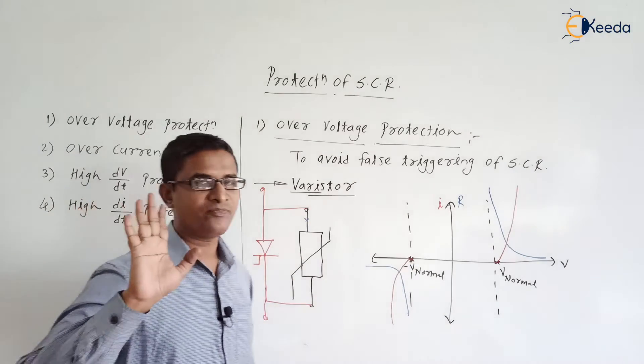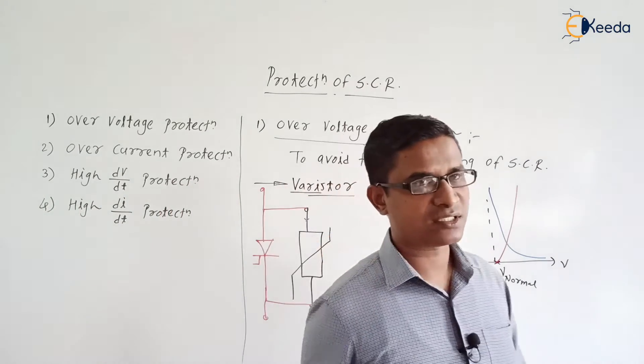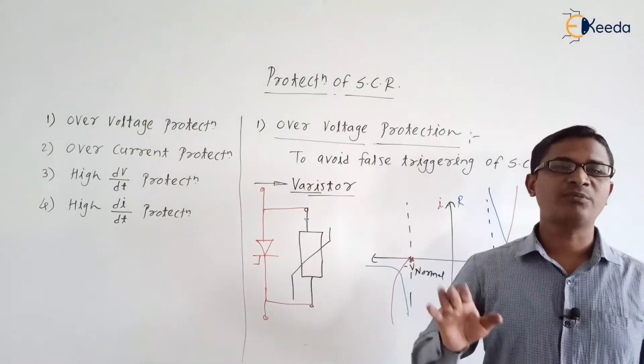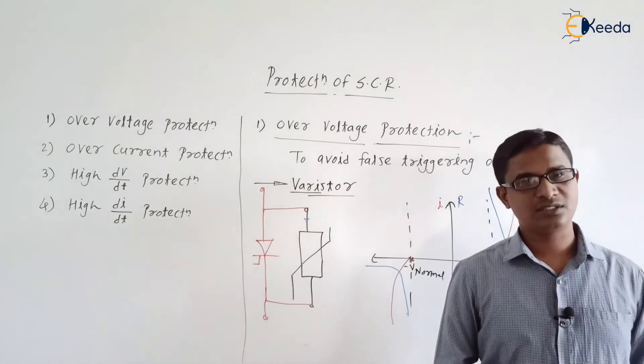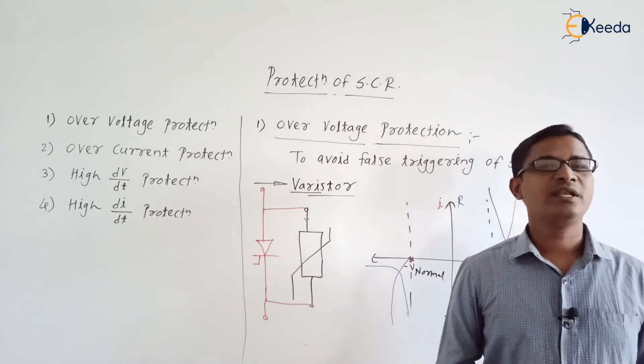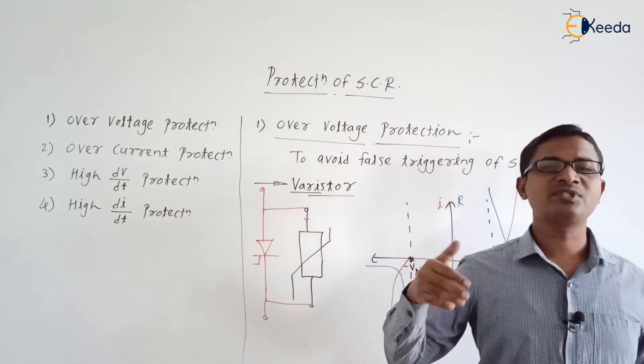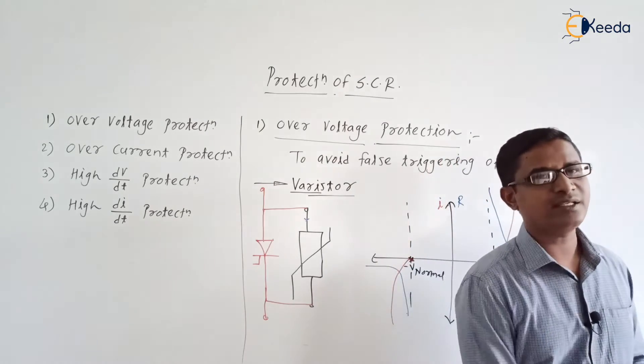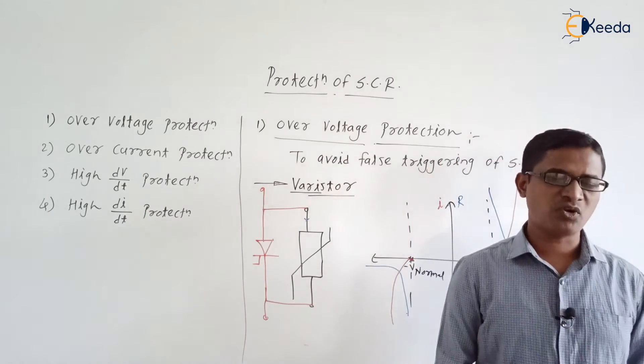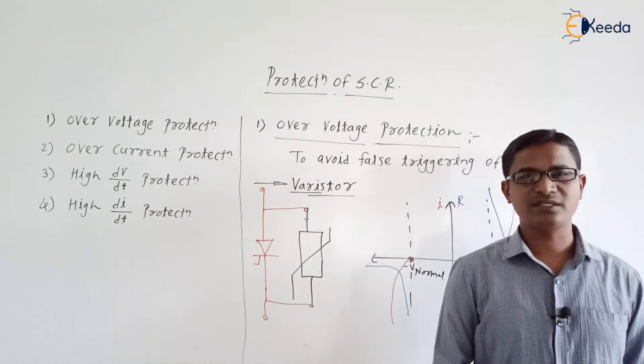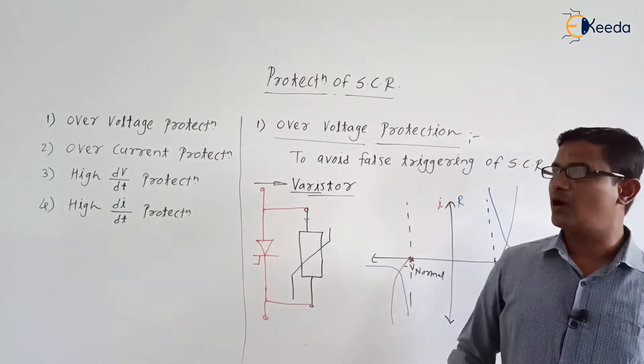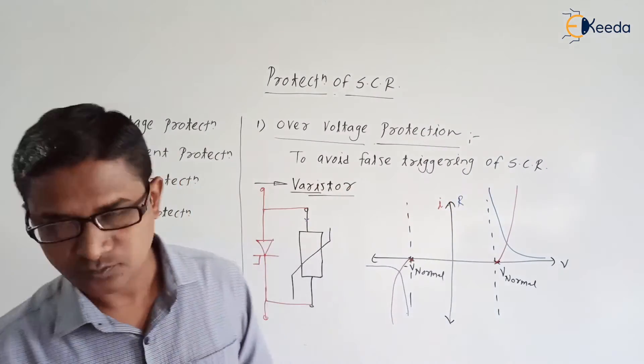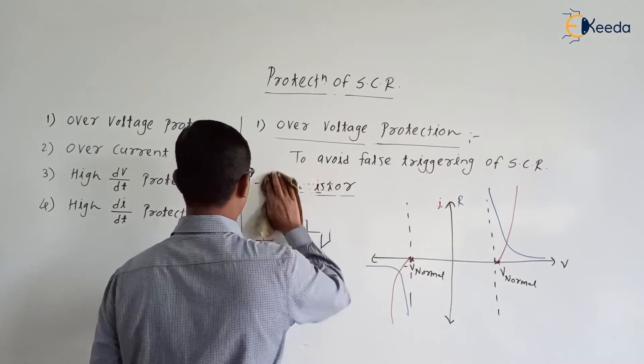In summary, the varistor is a variable resistor that offers a very high resistance during normal working voltage — effectively infinite. When the voltage becomes abnormal, its resistance decreases suddenly by a very large amount. In this way, the varistor protects the SCR against over voltage. Now let us discuss over current protection.